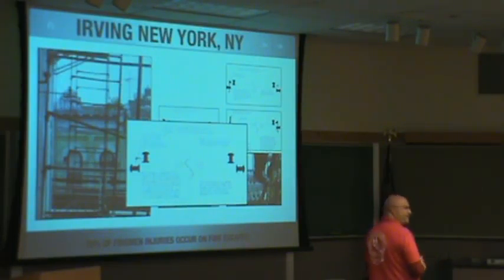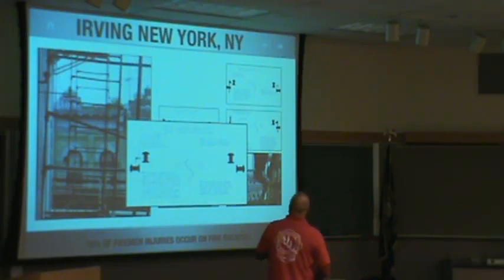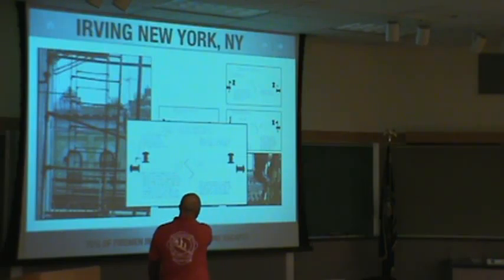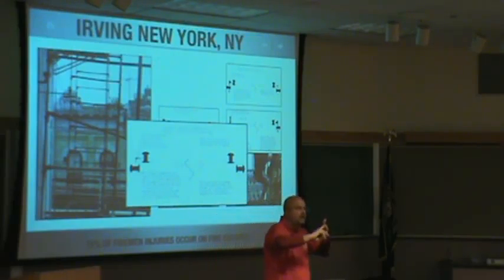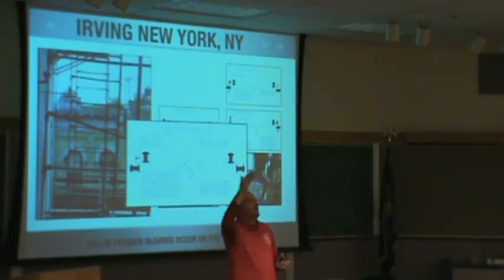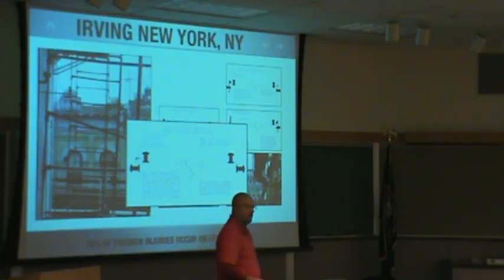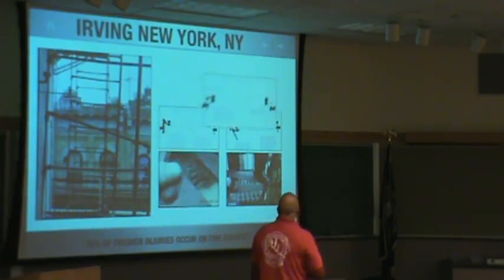How do you stop it from getting air? You seal it with paint — that's what they did 100 years ago. So as long as you keep it painted, it'll never get the air it needs to grow rust. You were supposed to keep your fire escape painted on average every three to five years. Every seal on a fire escape has broken, allowing air to get to those unprotected pieces. What you were supposed to do 50, 75, 100 years ago is lightly wire brush it and paint it every three to five years. Nobody did that. So they let it go to the next phase — they painted over the rust that was there.